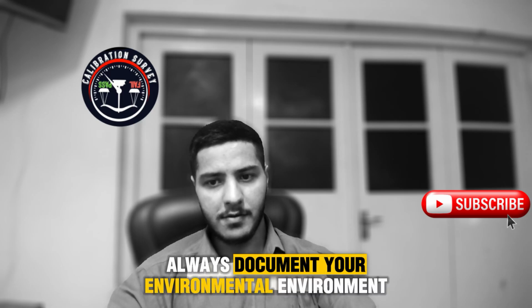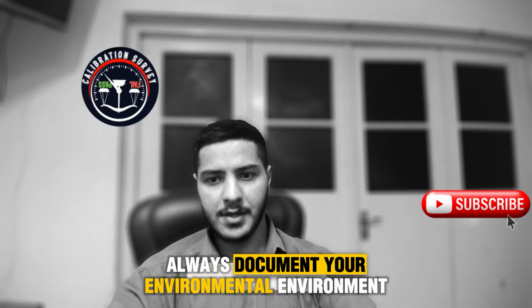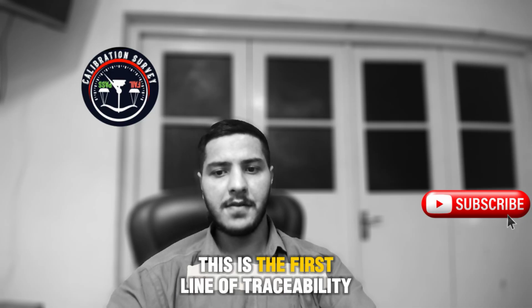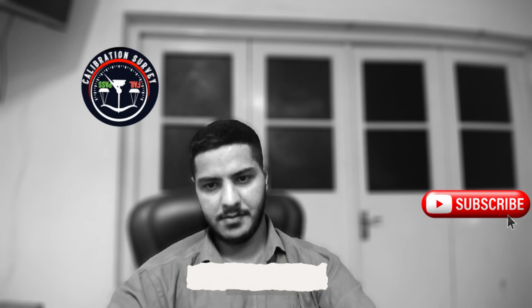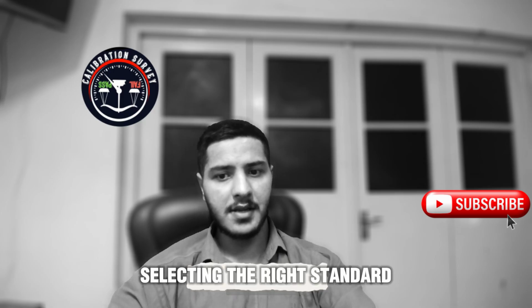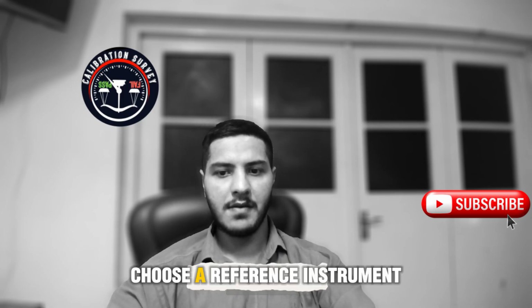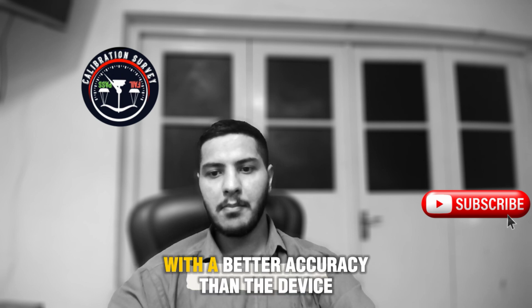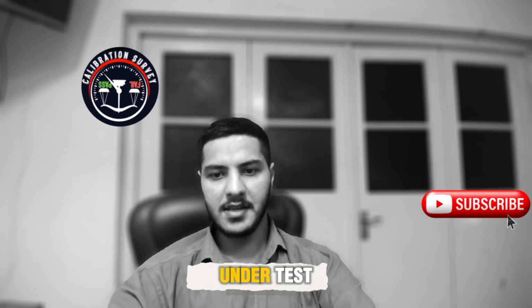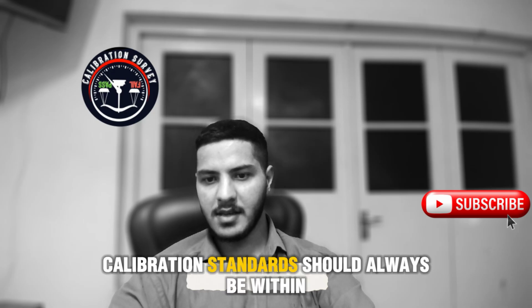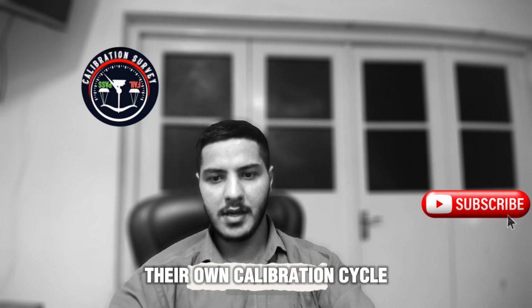Always document your environment. This is the first line of traceability. Selecting the right standard. Choose a reference instrument with a better accuracy than the device under test. Calibration standards should always be within their own calibration cycle.